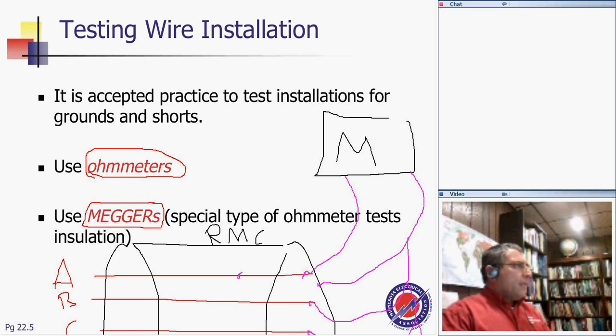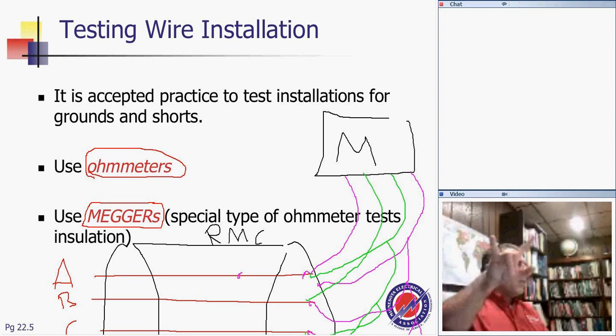Then you do the same thing for phase B, and you do it for all the phases. Phase B now needs to go to the conduit. I need to go phase B and C, and also phase C and the neutral. So in short, guys, you measure the impedance between every phase and the other phase, every phase and the neutral, and every phase and the conduit. If it's extremely high, this means the insulation is perfect, no problem.